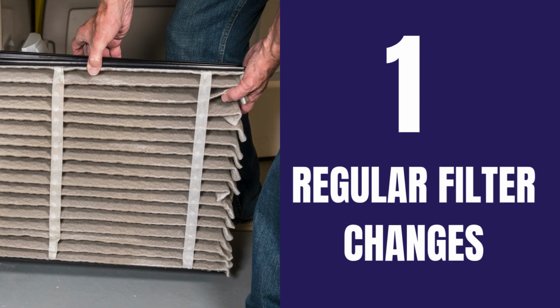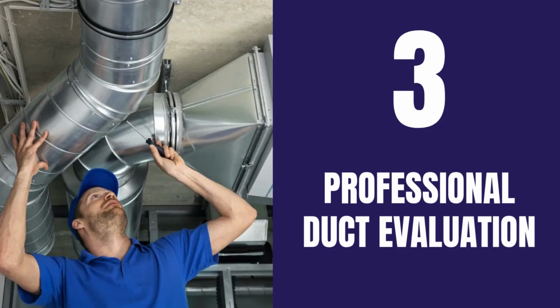Prevention and maintenance. Good news is that maintaining proper static pressure isn't complicated. Here are the key preventative steps. Number 1, regular filter changes. Don't wait until your filter looks dirty. Set a regular schedule based on your home's needs, typically every 1 to 3 months. Number 2, keep your vents clear. Ensure all supply and return vents are unobstructed. Even closing a few vents can significantly impact system-wide static pressure. Number 3, professional duct evaluation. Have your ductwork evaluated to ensure it's properly sized for your system. This is especially important if you've upgraded your HVAC unit without upgrading the ductwork. Number 4, regular static pressure checks. During your maintenance visits, insist that your technician measure and record static pressure readings. This creates a baseline to track changes over time.